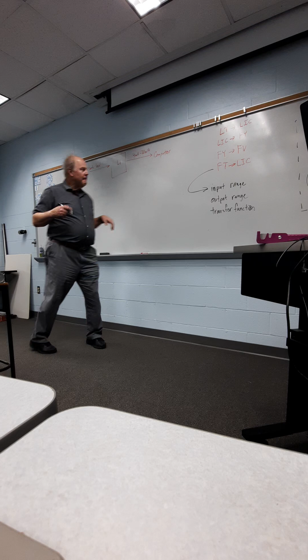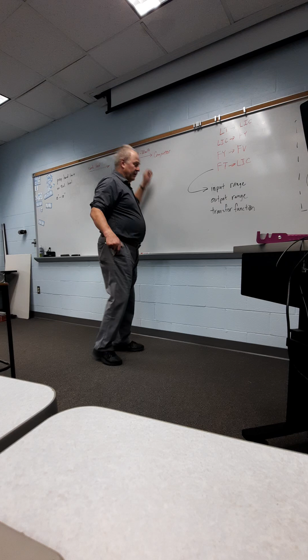Why? Can we have a negative tank level? No. Once it's drained to 0, it's drained to 0, it's dry. It can't be extra dry. It's just dry. So 0 is the bottom. What's the top limit? In this case, 10 inches, because anything above that gets flowed out of the tank. So some proportional bands are set for you by a physical limitation. That's all it can do. Possibly even on signals like 4 milliamp to 20 milliamp, not all receivers can adapt and say, I can handle 2 milliamp, I can handle 24 milliamp. They maybe can, maybe can't, but usually in most communication systems, we arbitrarily set 4 milliamp to 20 milliamp bounds, saying if it's less than 4 milliamps or greater than 20 milliamps, we make that an illegal signal.